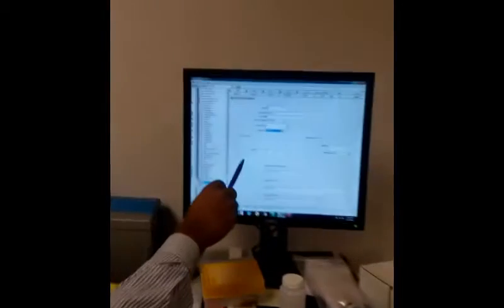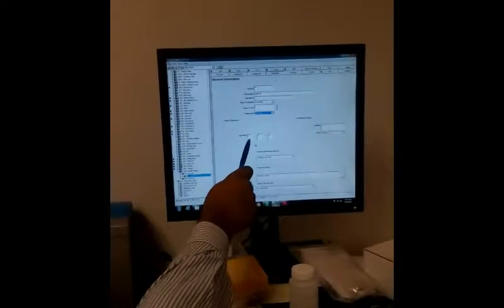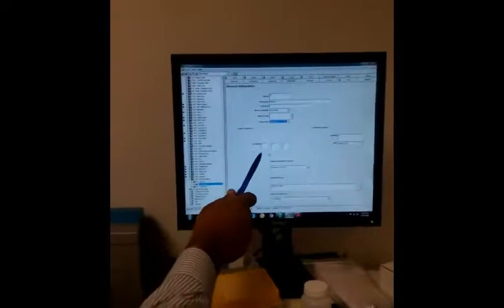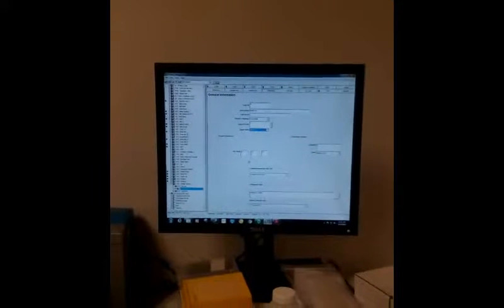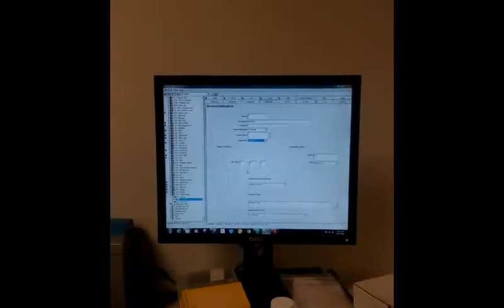So what does it mean by ISO 4/6/14? It's an example. Basically saying this is your target cleanliness. So the default is 21/18/15, but this is just an example. The particle size? That's probably going to be the ISO codes. So if you're familiar with ISO codes, each one of those numbers reflects a certain range of how many particles for less than 4 micron, then 6 micron, then 14 micron.